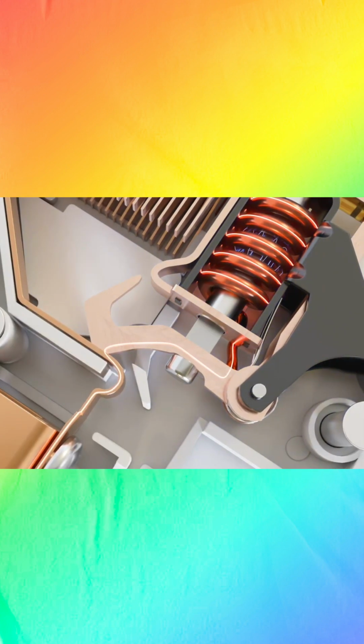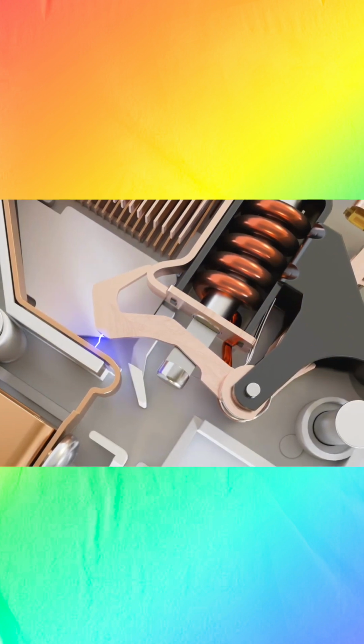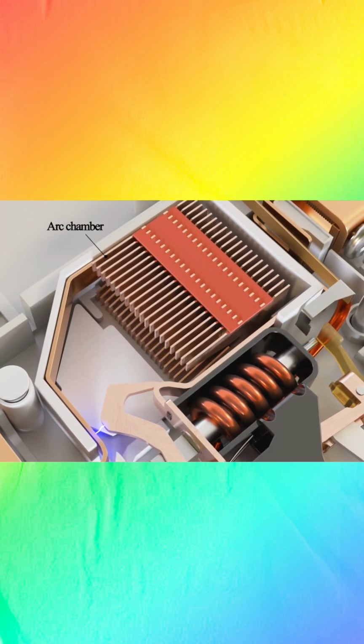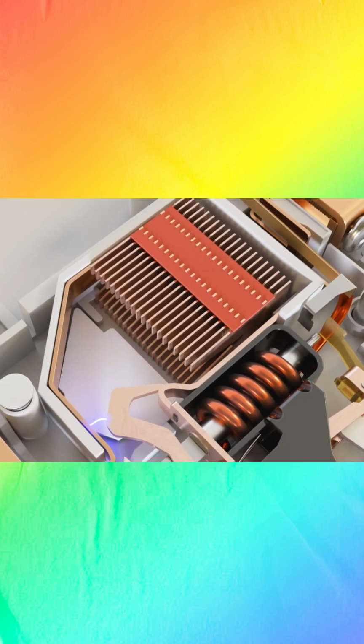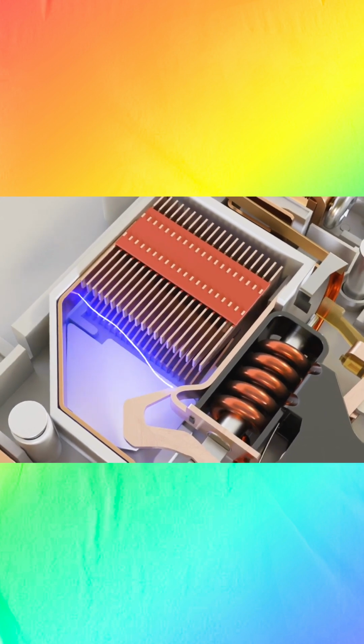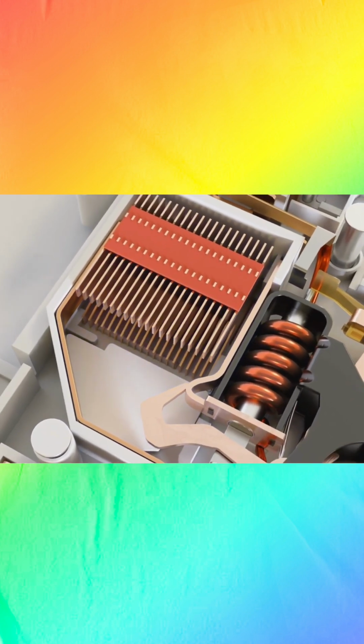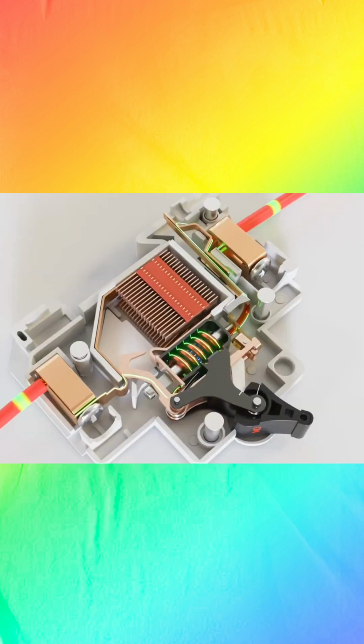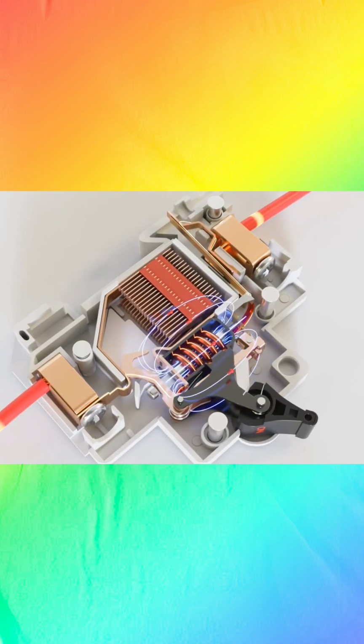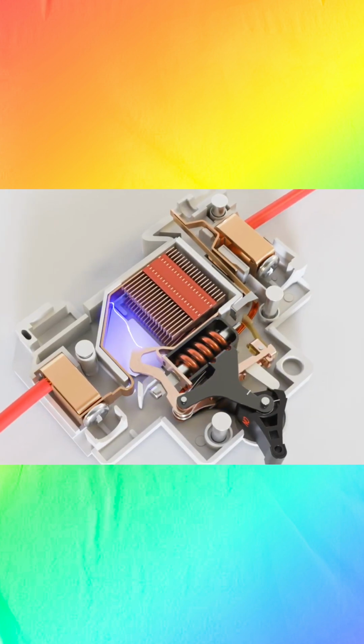This sudden interruption of current can cause an electric arc to form between the contacts. The temperature of the electric arc can go as high as thousands of degrees Celsius, which can easily cause damage to our MCB. To solve this issue, we use a component called an arc chamber. An arc chamber is designed to split this arc into smaller pieces so that the energy of the arc can safely dissipate. And that's how an MCB protects the electrical system from short circuit.